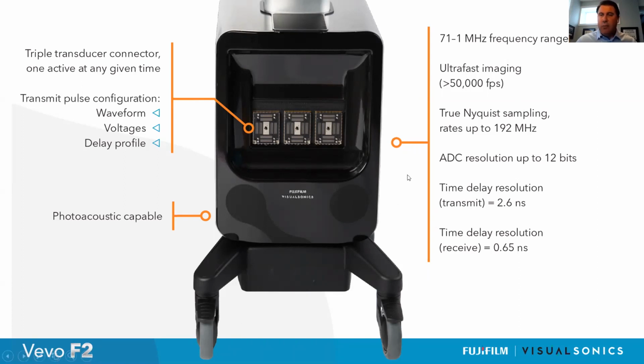As mentioned, it is photoacoustic capable, and a number of the key specifications, clearly the frequency range, 71 down to 1 megahertz. The system is capable of ultra-fast imaging, over 50,000 frames per second. It does use a true Nyquist sampling rate up to 192 megahertz, ADC resolution up to 12 bits, and time delay resolutions on the transmit side of 2.6 nanoseconds, and on the receive side, time delay resolutions of 0.65 nanoseconds. So these are very precise delays which are driven by these high frequency electronics and allow us to do this very high precision beam forming and image formation, which I'll show you some examples of shortly.